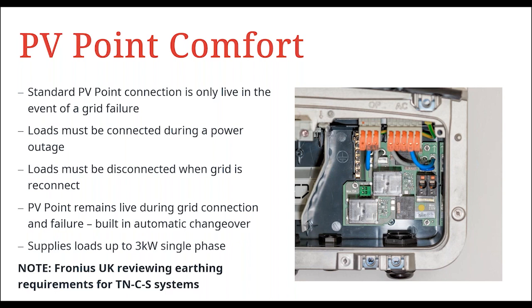First of all, we have the PV point comfort circuit. So the standard PV point circuit is the three terminal outlet you can see on the screen there, and that provides power only when the grid is failed, when there's a power cut. So in normal operation, PV point is switched off and there's no power from it. When the grid dies, that circuit becomes live and you're able to connect in essential loads, maybe your fridge freezer, for example. The only problem is once the grid is re-established, that circuit will switch off and you'll go back to the mains. The new PV point comfort circuit enables that outlet to remain permanently live.